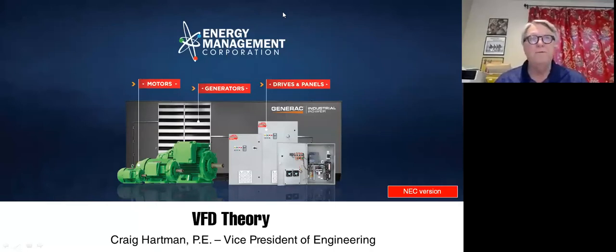We are going to do VFD Theory today, and next session, we'll let you know when that is due to the July 4th holiday and so on. But the next session, we will do startup maintenance and troubleshooting of VFDs, and we'll actually go out in our lab and have one of our techs go through that. And then we'll have harmonics. We talked about active harmonic correction before, but in the harmonics, VFD harmonics, we'll talk about every single method of harmonic correction that is available on VFDs, and we will talk about the advantages and disadvantages of each, show you some real-world testing results, and we will, of course, cover IEEE 519 and introduce the subject of harmonics.